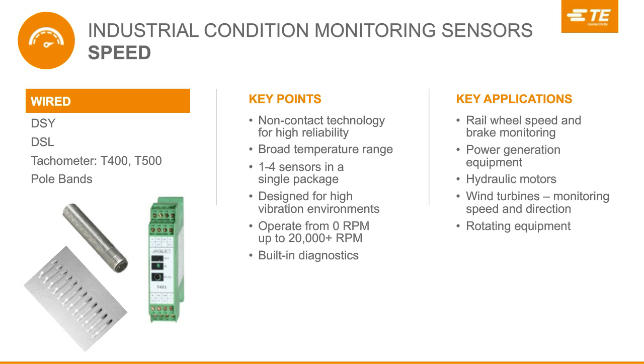TE can also provide the corresponding pole bands that are used as targets for the speed sensor, as well as tachometers and other instrumentation. The speed sensors can be used for speed feedback and control, and can also be used to detect bearing wear and resonant vibration as part of a total machine health monitoring system.